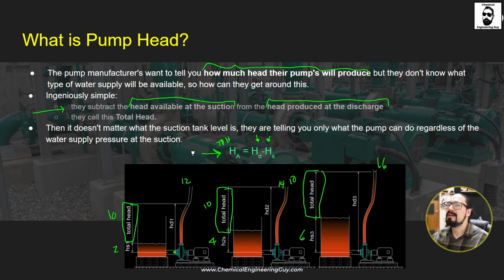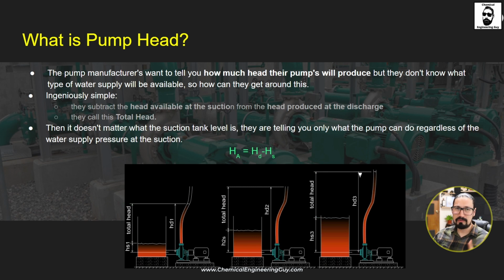Thankfully, it doesn't matter what the suction tank level is — they're only telling you what the pump can do, regardless of the water supply pressure. So here we have a low pressure on the suction line, a normal pressure in the suction line, and a very high pressure in the suction line, giving different values. As stated before, the only point that remains constant is the total head — thankfully, that gives us a way to turn around and determine the total head of the line.